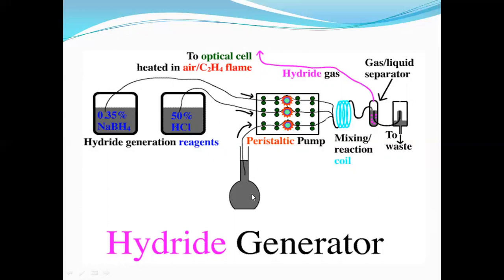The sample is at the bottom. These three solutions — the sample, sodium borohydride, and 50% HCl — are mixed using peristaltic pumps and then accelerated into a mixing or reaction coil. From the reaction coil, hydrides of the different metals are generated. A gas-liquid separator then separates the hydride gas, while waste is drained out. The hydride gas is then directed to the optical cell and heated in an air-acetylene flame.